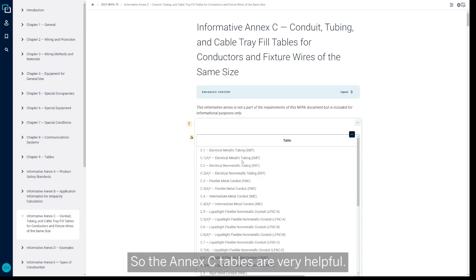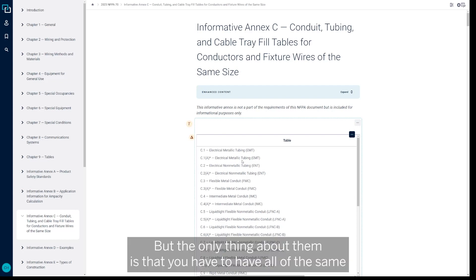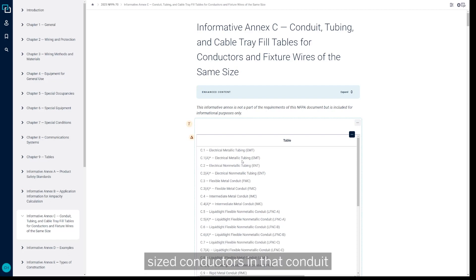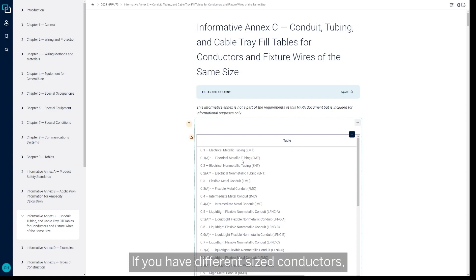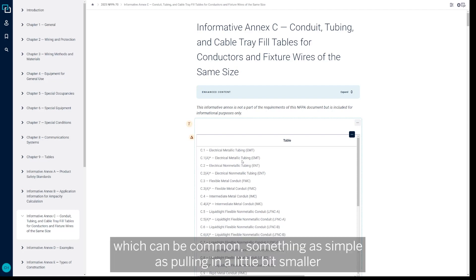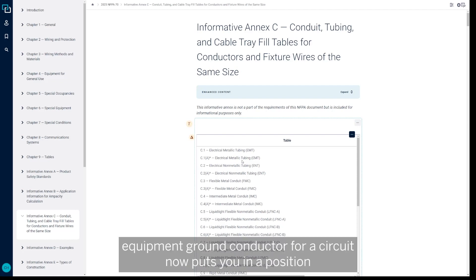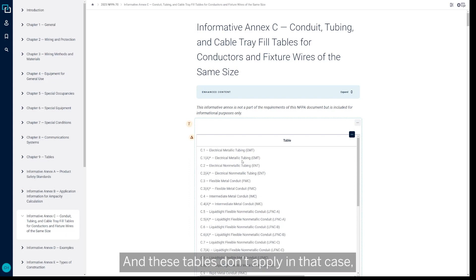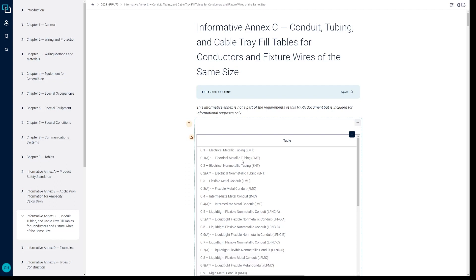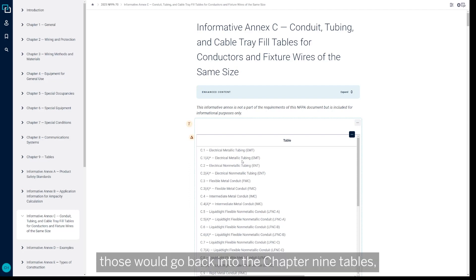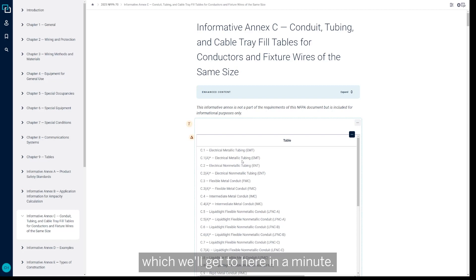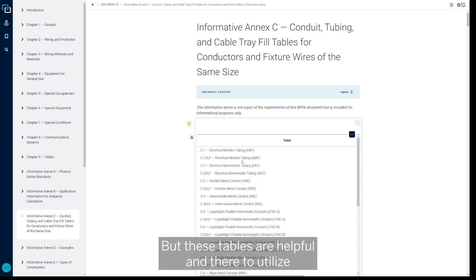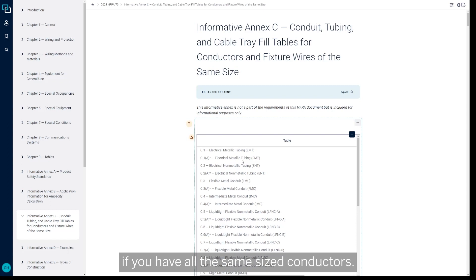So the Annex C tables are very helpful, but the only thing about them is that you have to have all of the same size conductors in that conduit in order to truly utilize these tables. If you have different size conductors, which can be common—something as simple as pulling in a little bit smaller equipment ground conductor for a circuit—now puts you in a position where you have two or more different size conductors within that conduit, and these tables don't apply in that case. Those would go back into the Chapter 9 tables, which we'll get to here in a minute. But these tables are helpful and there to utilize if you have all the same size conductors.